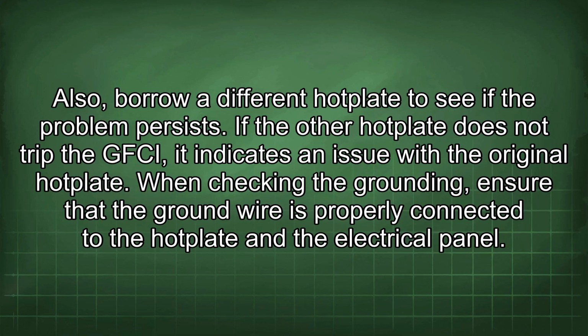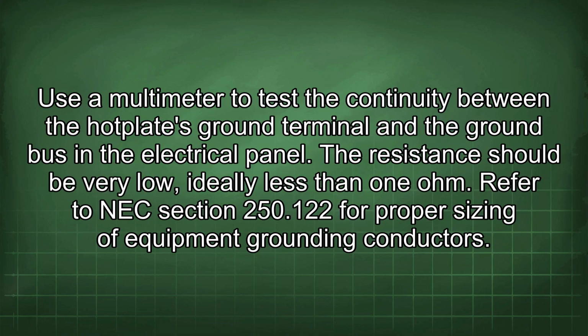When checking the grounding, ensure that the ground wire is properly connected to the hot plate and the electrical panel. Use a multimeter to test the continuity between the hot plate's ground terminal and the ground bus in the electrical panel. The resistance should be very low, ideally less than 1 ohm. Refer to NEC section 250.122 for proper sizing of equipment grounding conductors.